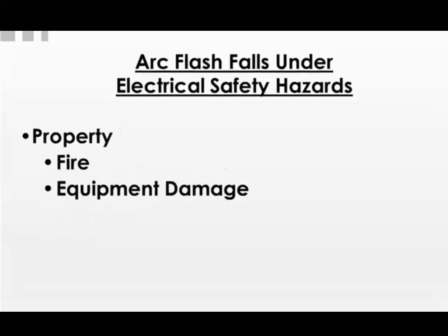Now, the main thing we're concerned about with arc flash protection is people. But arc flashes and arc blasts can cause significant property damage. It can create fires. It can create equipment damage. I've seen whole plants taken down, or portions of a plant taken down for an extended period of time. That's a lot of lost downtime. And in addition to lost downtime, having your plant down creates, in and of itself, pressure to get the plant back up and running, right? So that creates upset conditions where maintenance workers, electricians, engineers, et cetera, are working under a lot of pressure to get things up and running, and that in and of itself can create opportunities for accidents to occur.